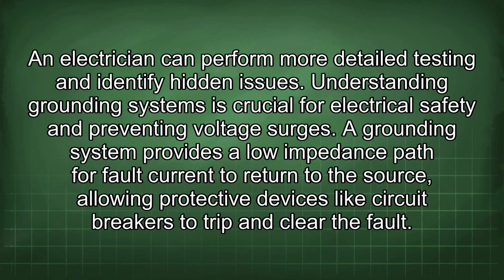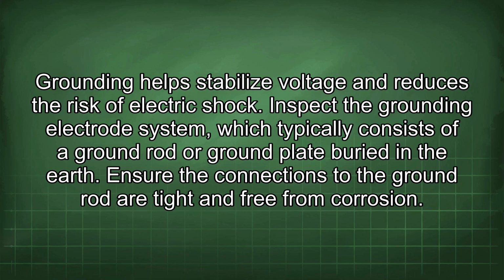A grounding system provides a low impedance path for fault current to return to the source, allowing protective devices like circuit breakers to trip and clear the fault. Grounding helps stabilize voltage and reduces the risk of electric shock.